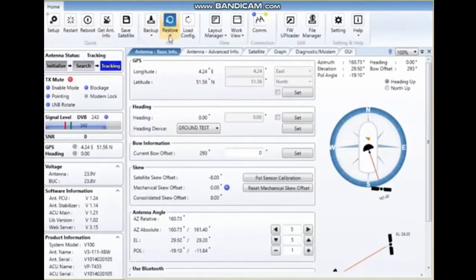Over here we've got two functions, the backup and restore function. The reason for taking a backup is that all this information which you now have calibrated will be stored inside the main control unit, inside the antenna. If you have problems with your MCU in a later stage and you need to replace it, it's nice to have a backup of this information in your laptop or inside the ACU, so you can restore that into the new MCU.